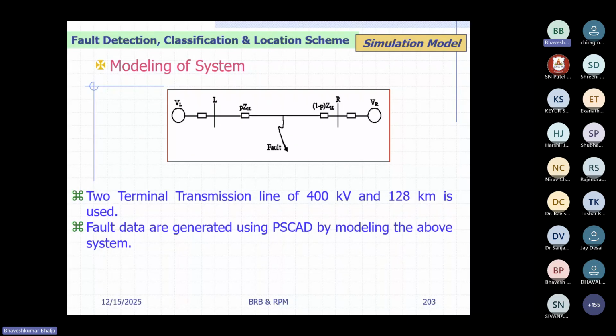The other parameter is fault resistance, right? Let's say a line to ground fault may occur through some tree limb or some other thing, or on an RCC surface or asphalt surface, depending. So fault resistance you can vary, and tower resistance also comes into the picture. Whenever a line to ground fault occurs, tower resistance comes into the picture, because you remember the cross arm, and the line to ground fault current flows through the tower. The tower has some resistance from 5 ohm to 50 ohm. This is also variable depending upon the environmental condition. That also you can vary.